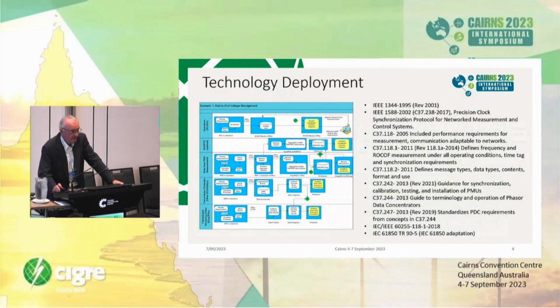with the standards and how these PMUs actually appear in terms of devices. On the left-hand side, it's just something I picked up from voltage measurements. It doesn't matter what it is. But the front end for a SCADA system is a remote terminal unit, as you know. However, in the substations, we potentially have standalone PMUs or PMU algorithms embedded in other devices, like protection relays or digital fault recorders and so on. So that's what is shown on the left-hand side.